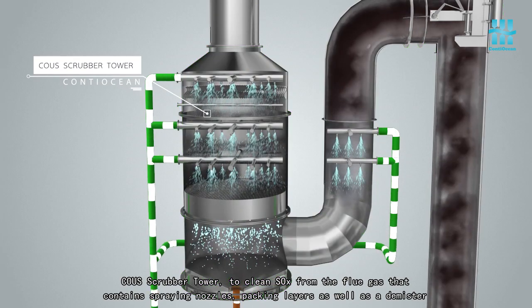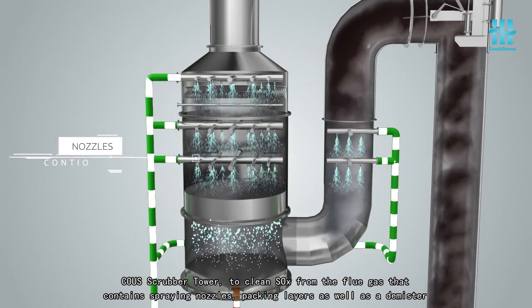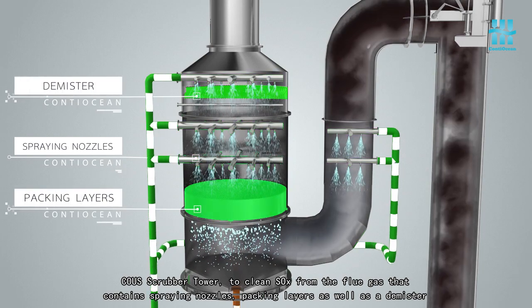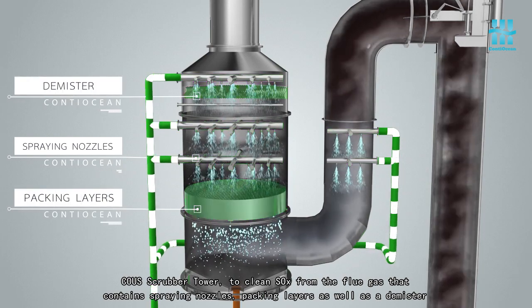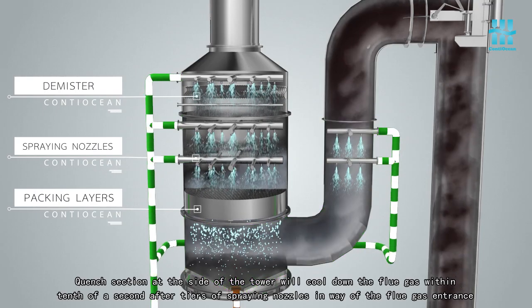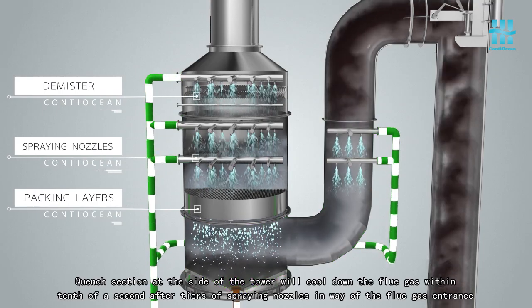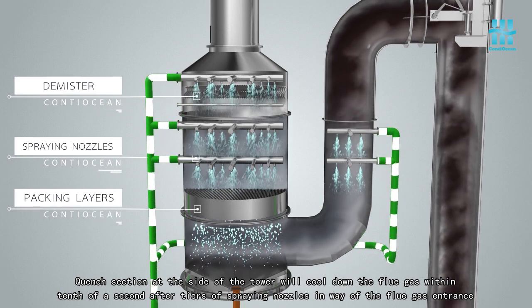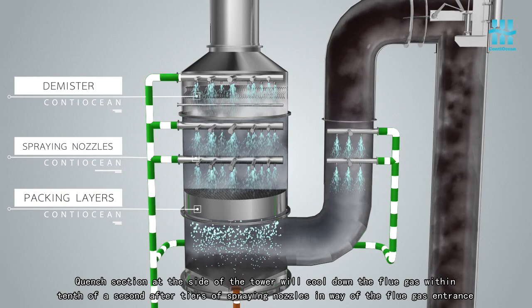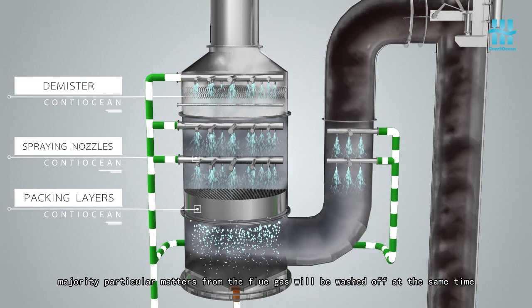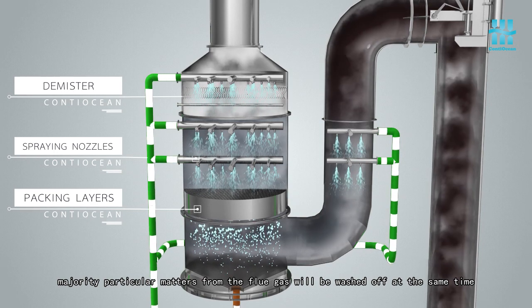COUS Scrubber Tower to clean SOx from the flue gas contains spraying nozzles, packing layers, as well as a demister. Quench section at the side of the tower will cool down the flue gas within tenth of a second after tiers of spraying nozzles in way of the flue gas entrance. Majority particular matters from the flue gas will be washed off at the same time.